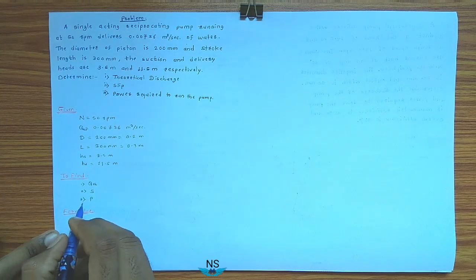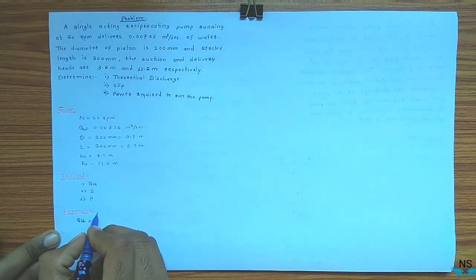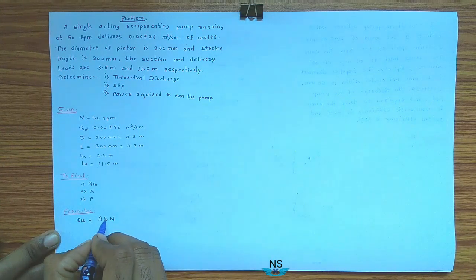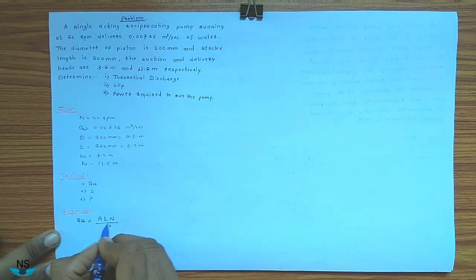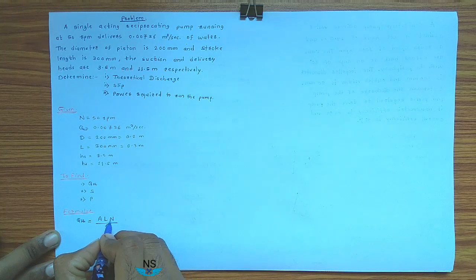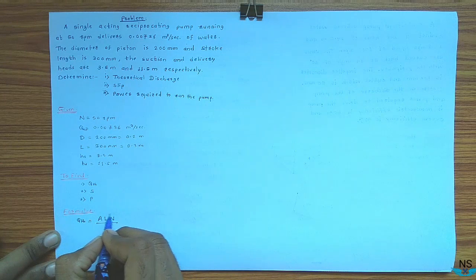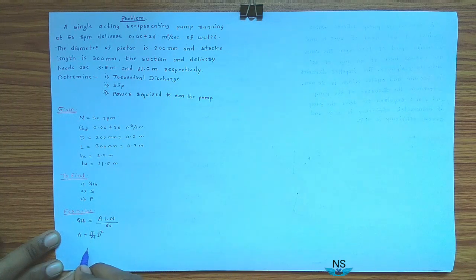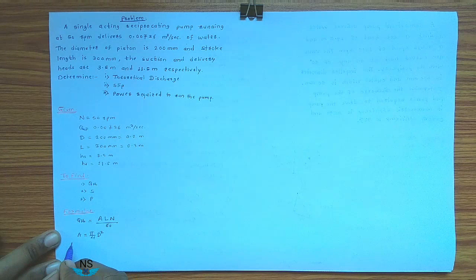For a reciprocating pump, theoretical discharge Q_theoretical is equal to area (A) into stroke length (L) into speed n in rpm, divided by 60. The division by 60 is to convert rpm into rps. Here A is the area of the cylinder, that is A = π/4 × d², L is stroke length, and n is speed in rpm.